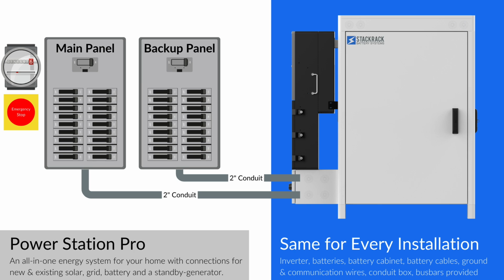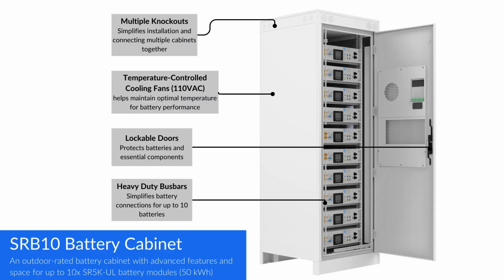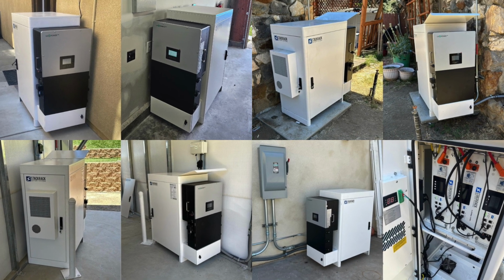Lastly, this is our SRB10 battery cabinet, which allows you to stack up to 10 batteries for 50 kilowatt hours of storage. This features bus bars that run along the inside of the cabinet from top to bottom, making it very easy to connect batteries in parallel for larger battery banks. And here are some installation pictures.